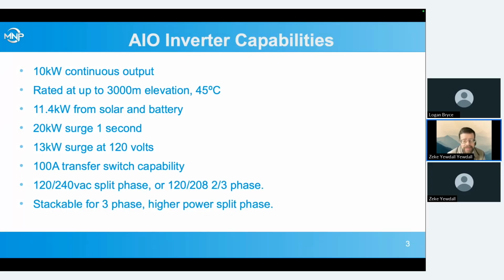Inverter capabilities: the 10 kilowatt continuous output, 120/240 split phase output, or you can use 3 of them to do 120/208 3-phase, with each of them picking up 2 of the phases and 3 of them creating the full 3-phase. We're rated for up to 3,000 meter elevation and 45 C ambient operating temperature. So it's pretty conservative in cooler temperatures and lower elevations sometimes.